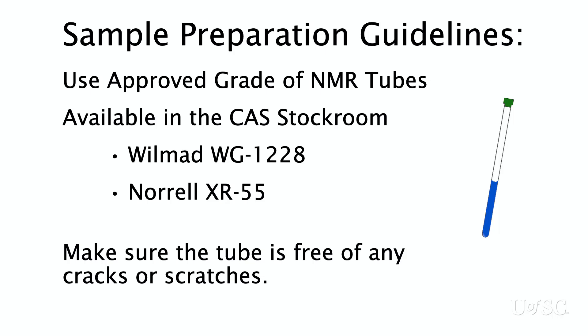You should inspect your tubes for any scratches or cracks. A broken sample that leaks into the probe can cause extensive damage and months of downtime.